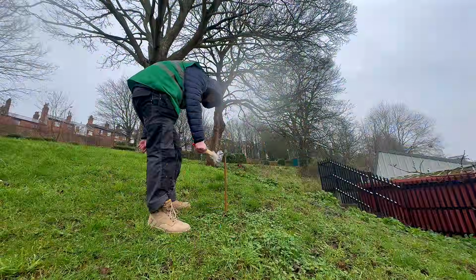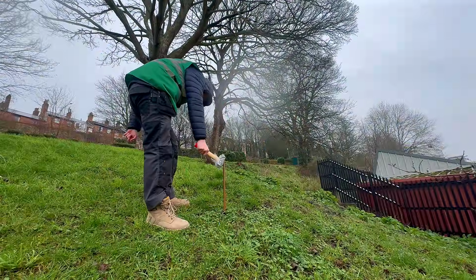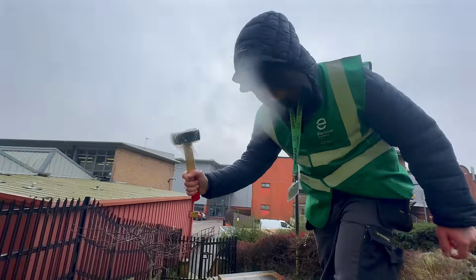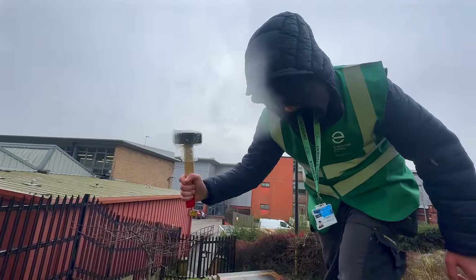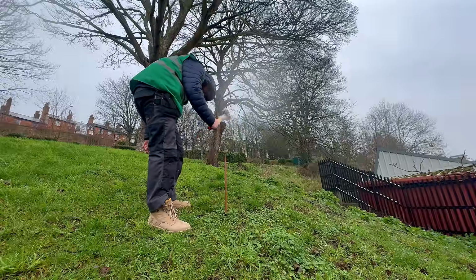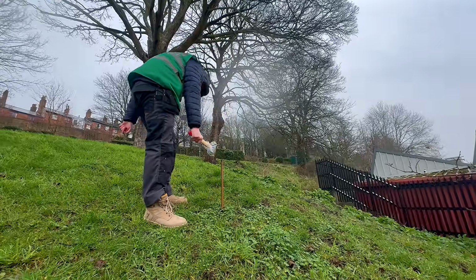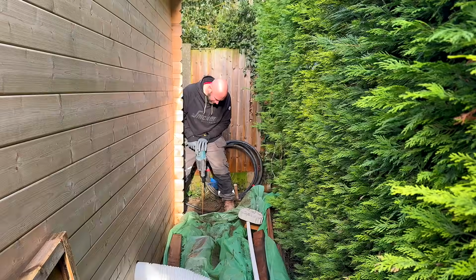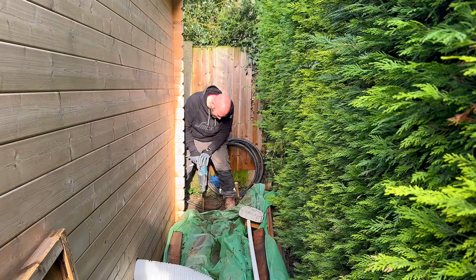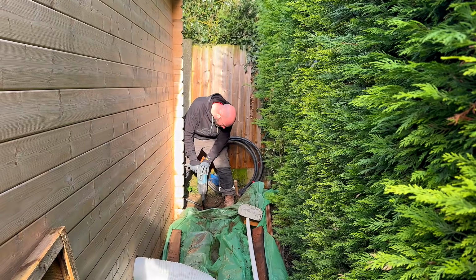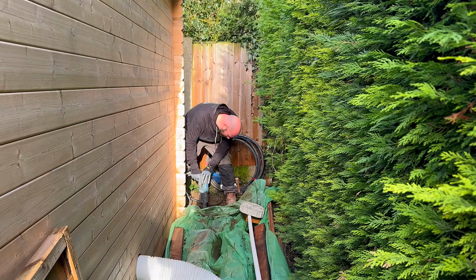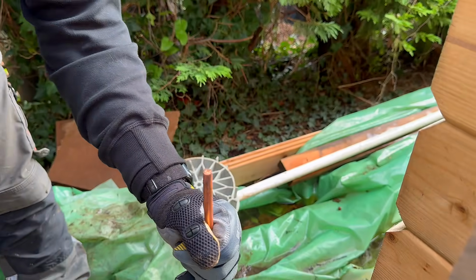Let's start with the electrode itself. In this case, we are using a driven earth rod, installed vertically into the ground, and depth matters here. The electrode needs to be deep enough to make good contact with stable soil, not just the loose material at the surface. In practice, this often means driving the rod down until only the inspection point is accessible. You may even need to extend the rod to drive down deeper to hit more stable soil, but we will only know that once we test.